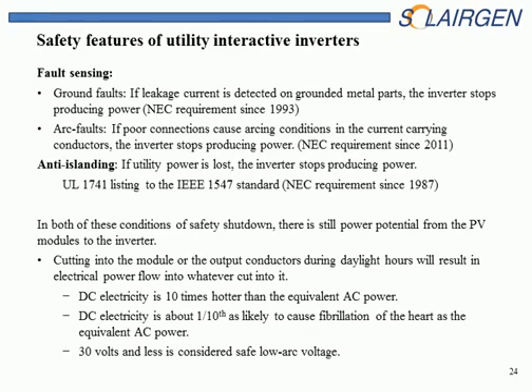So we consider anything below 80 volts to be fairly safe against arcs, and anything below 30 volts to be absolutely safe against any kind of electrical shock. I've touched 50 volt systems on battery banks and have not been shocked, so I really think that 50 volts is the safe zone, but for the sake of extreme caution, the NEC states that 30 volts or less is considered safe.